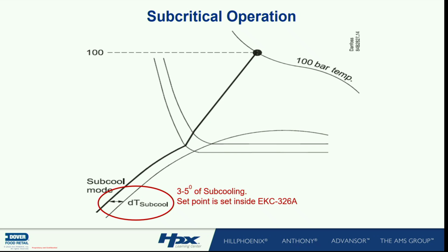So, somebody tell me what the pressure at 70 degrees is. The pressure at 70. What is it? 838. All right. So let's say it's a nice 70-degree day. We're running at 738. We good? As we're running through the system, the high pressure control valve is regulating. He's regulating for me. He's at 44%. What is he doing? So I got to create subcooling.